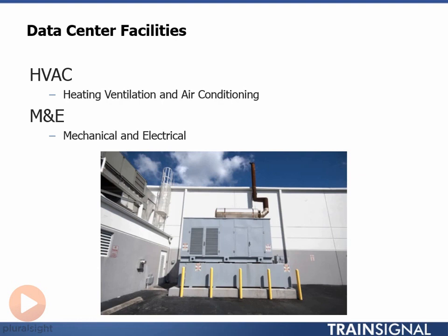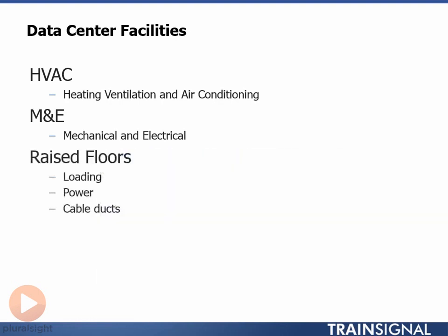We also talked briefly about raised floors. Raised floors are common in data centers as they allow power and network cabling kit to be kept neatly out of the way. It's common for power to IT kit to be provided by 16 amp, 32 amp or 63 amp commando sockets that are placed in the floor void beneath the data center racks. These power feeds then have armoured cables all the way back to the PDUs that we showed earlier in our floor plan, where each cabinet is individually fed and fused with a breaker so that each can be individually isolated.